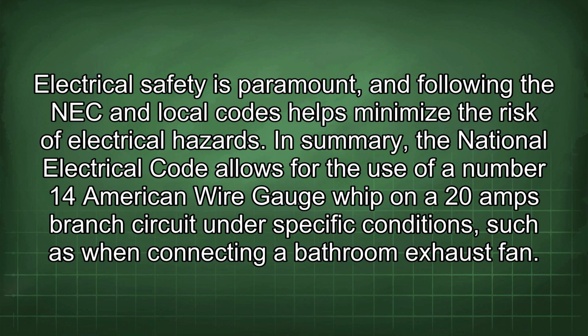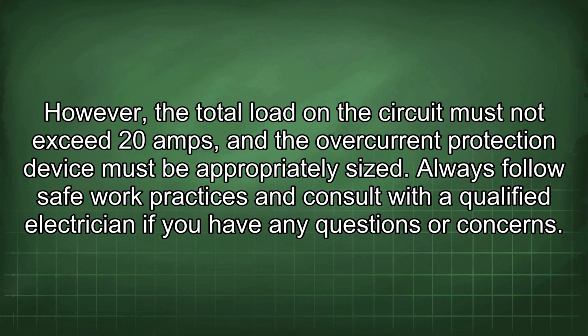In summary, the National Electrical Code allows for the use of a number 14 American wire gauge whip on a 20 amps branch circuit under specific conditions, such as when connecting a bathroom exhaust fan. However, the total load on the circuit must not exceed 20 amps, and the overcurrent protection device must be appropriately sized. Always follow safe work practices and consult with a qualified electrician if you have any questions or concerns.